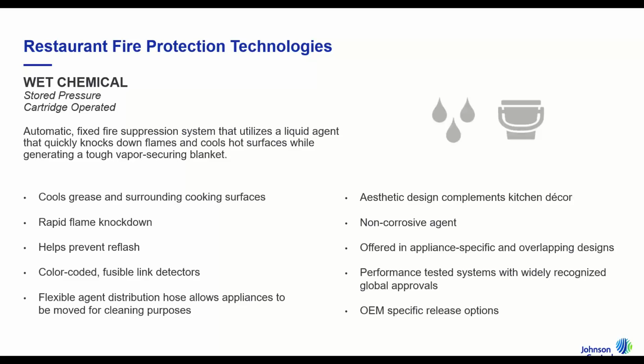There are fusible link detectors in the mechanical style offerings, and our fusible links are color coded. So they're temperature specific to the application, and the color coding identifies what that temperature is. For easy knowing of what detector is up there, you can pull out the filter, look up and understand what that detector temperature is. As I said, it is a fixed suppression, so they're mounted in the hood. However, we do have a flexible agent distribution hose for appliances that require nozzles and piping to be fixed to it. So it can be moved for cleaning of the restaurant on a regular basis.